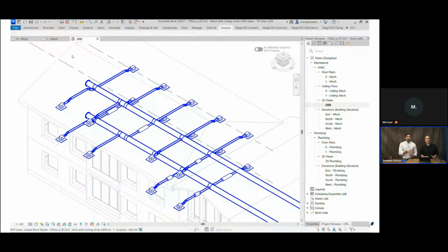So very quickly, we have a project where not only have we calculated it, but we've also solved our sound problems. We also flagged up areas that might be a concern, where you may need to look at it either on the design side or maybe on a requirement side. If we have a room where we really need 23 dBA, then maybe we need a different way of looking at that system. But that is impressive.